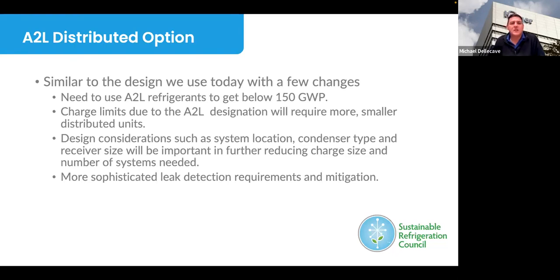That's what you would need to keep each one of those systems around to meet the codes. Design considerations such as the location of your equipment, the condenser type, the receiver size are all extremely important as you're looking to reduce that charge even further, to reduce the amount of equipment that you have.